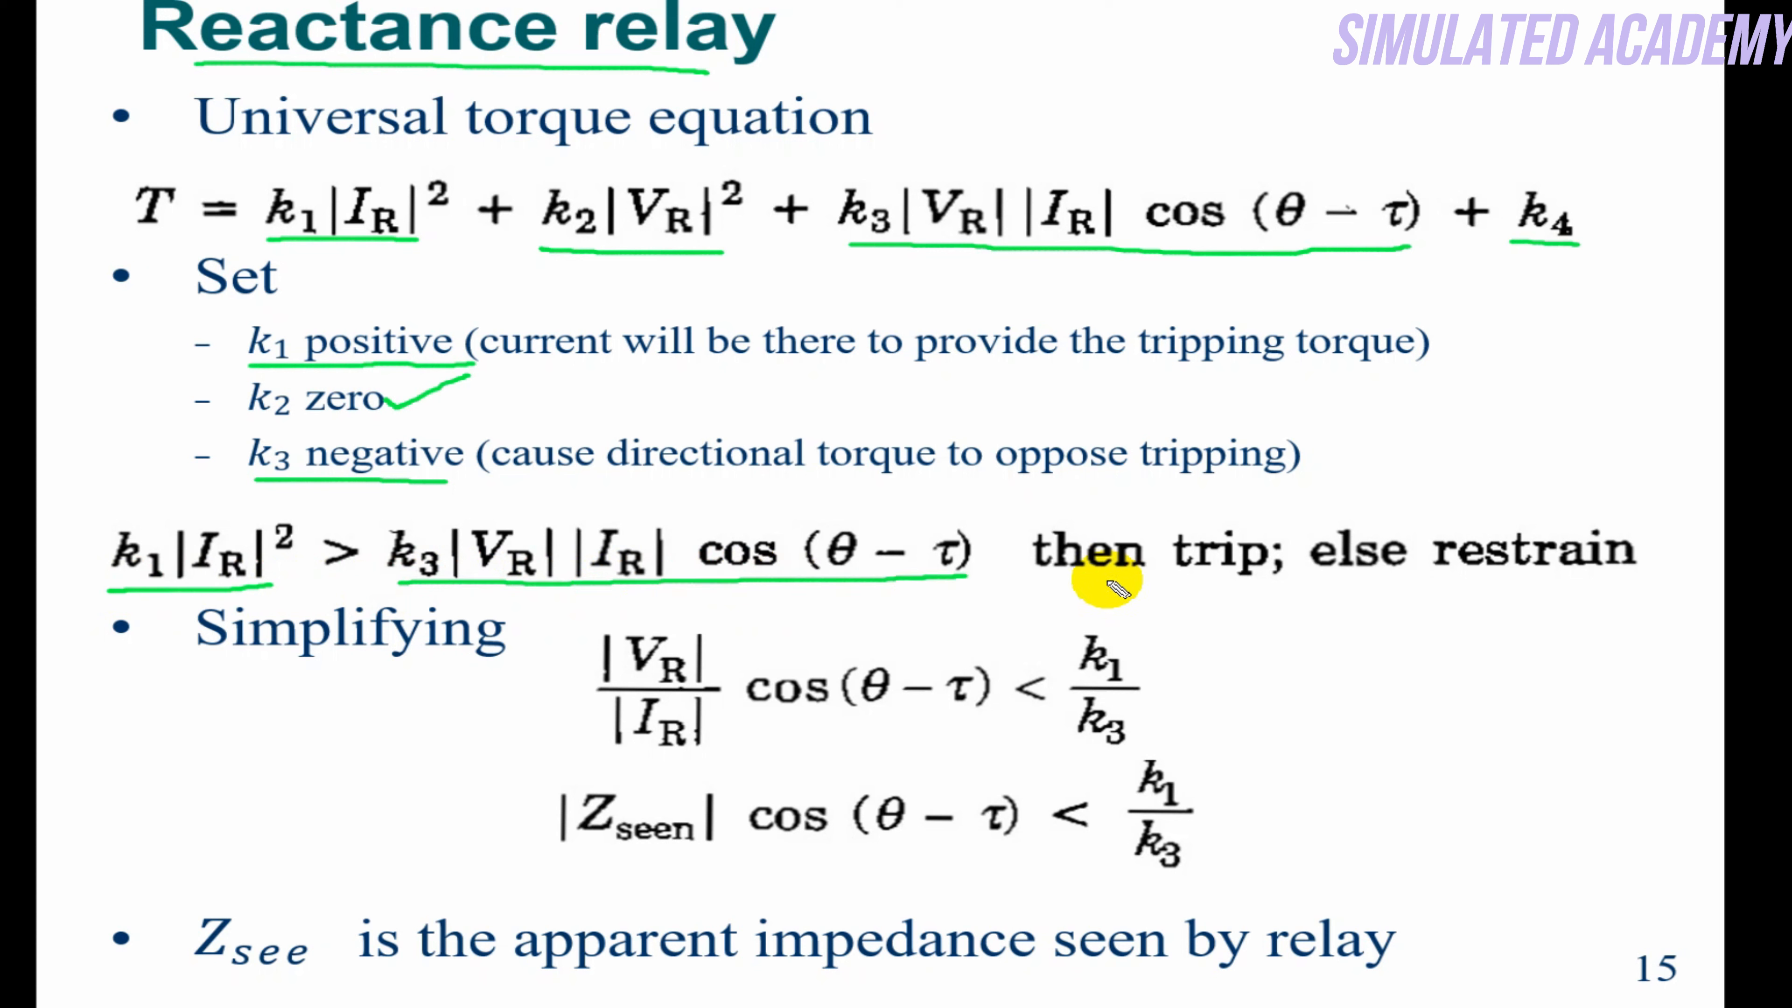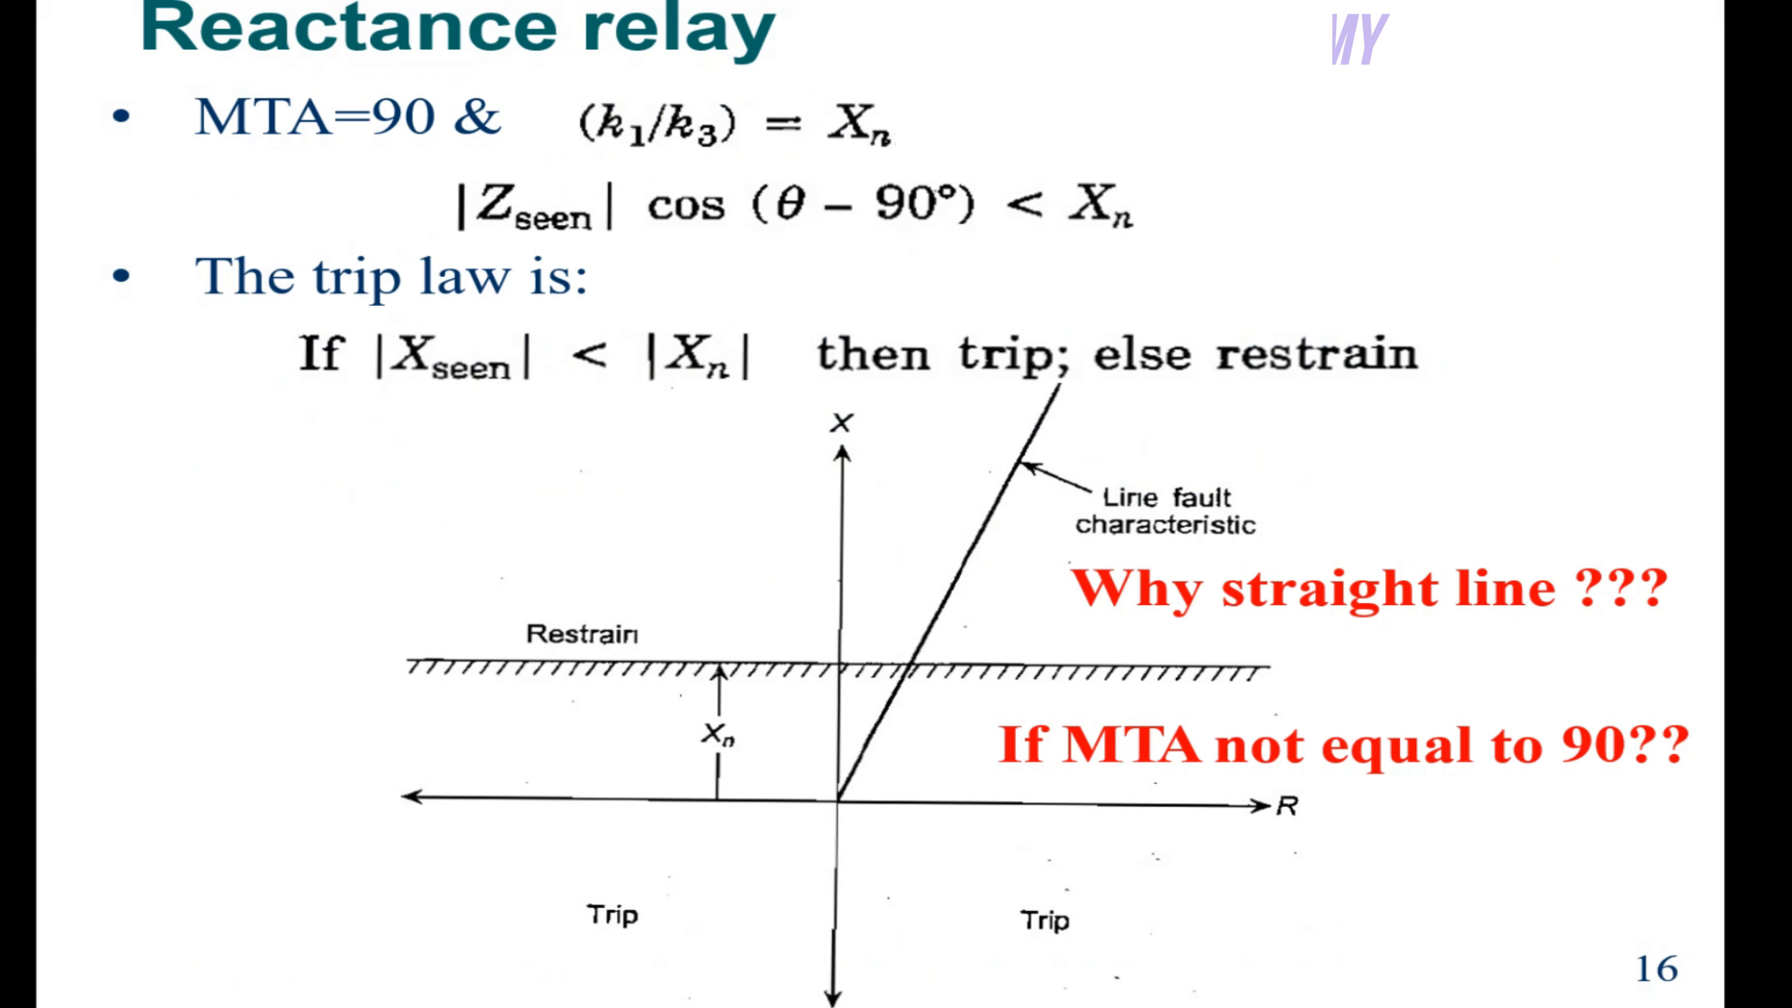If I simplify, |Z_seen| cos(θ - τ) is less than or equal to k1/k3, where τ is the maximum torque angle and θ is the angle between current and voltage. Z_seen is the apparent impedance seen by the relay. If the relay calculates impedance from current and voltage, this is called Z_seen.